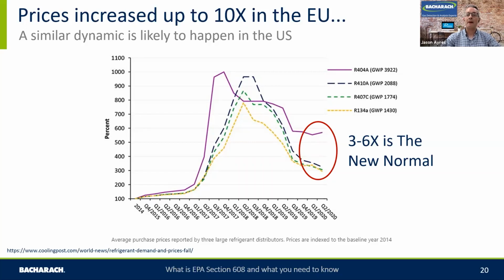And this was all about the availability of them on the marketplace. With the step down in the amount of refrigerant on the marketplace, refrigerant manufacturers are there to sell raw pounds of refrigerant. So they started to reduce back 404A and bring in lower GWP alternatives. So that drove supply and demand. Also, people were worried about keeping their existing systems up to date. So there were huge price increases. Those prices have come down over time, but they're still much higher than they were 10 years ago. So what does that mean? Containment is really important. Identifying and keeping refrigerant loss to a minimum, not just to protect the environment, but there could be a huge financial burden as well as part of the organisation.